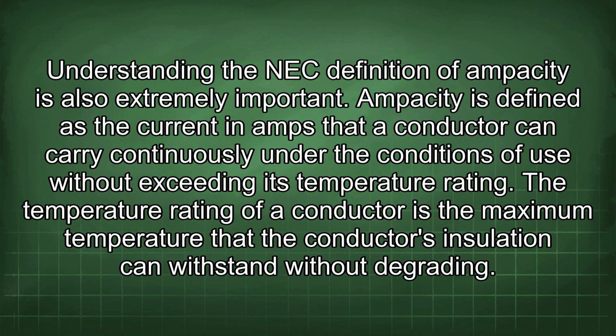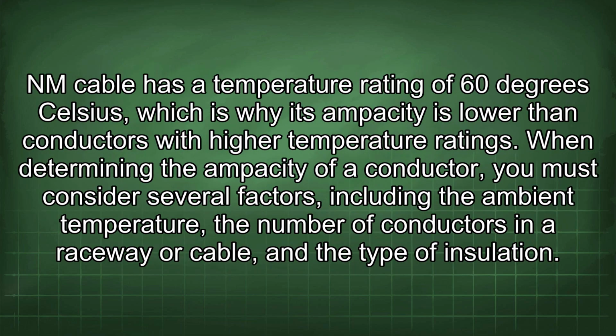Understanding the NEC definition of ampacity is also extremely important. Ampacity is defined as the current in amps that a conductor can carry continuously under the conditions of use without exceeding its temperature rating. The temperature rating of a conductor is the maximum temperature that the conductor's insulation can withstand without degrading. NM cable has a temperature rating of 60 degrees Celsius, which is why its ampacity is lower than conductors with higher temperature ratings.